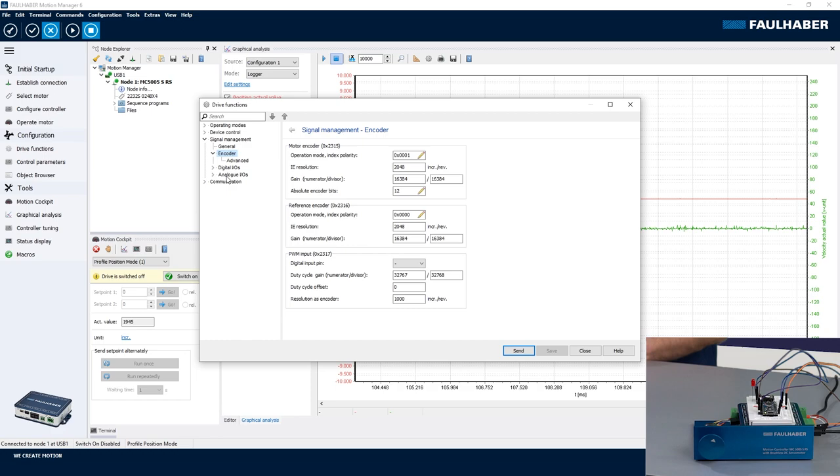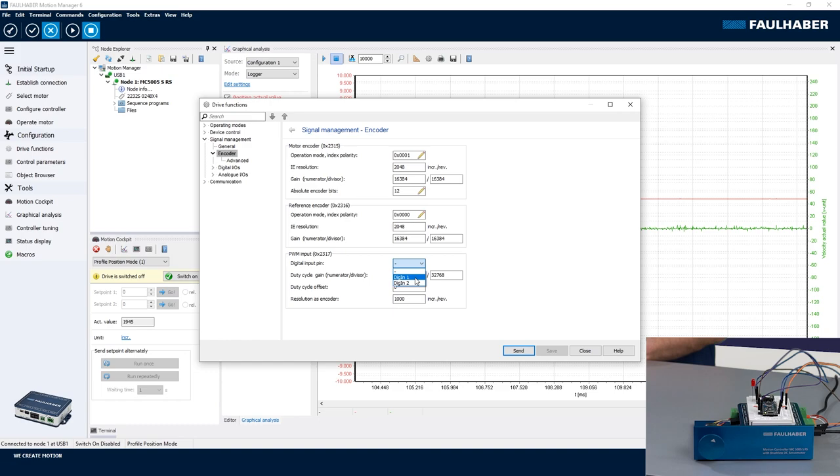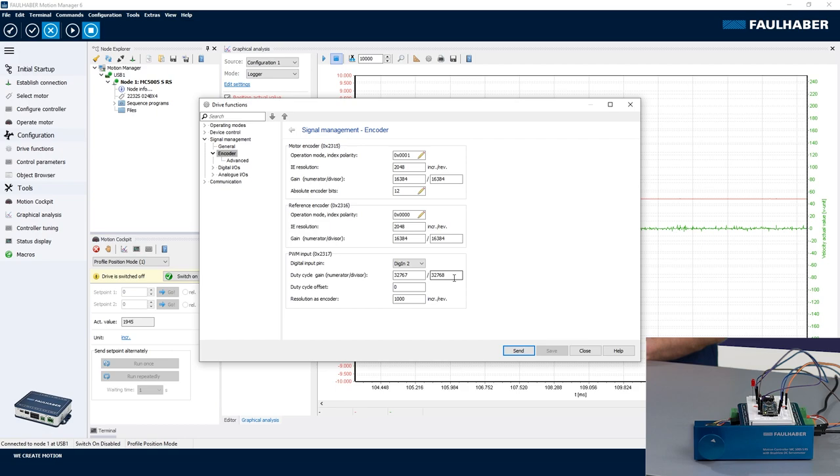It's again in the encoder section, same as for the gearing and the step mode. First is to select the digital input that I'm using here, so it's the digital input 2 that the PWM is connected to. And then consider the scaling, raw scaling for the full 0 to 100 percent is the 15 bits, so 0 to 32,767 counts.